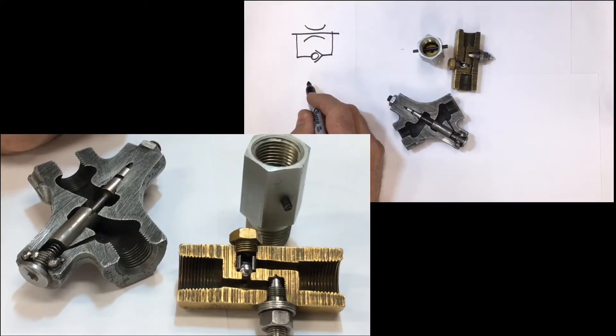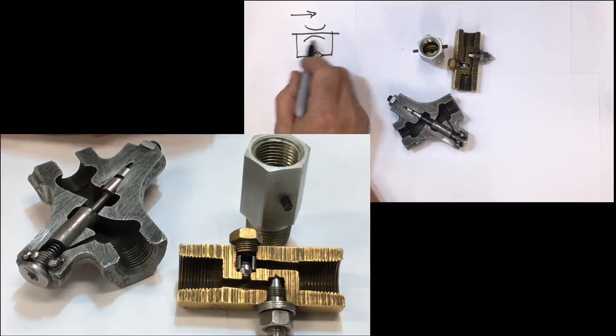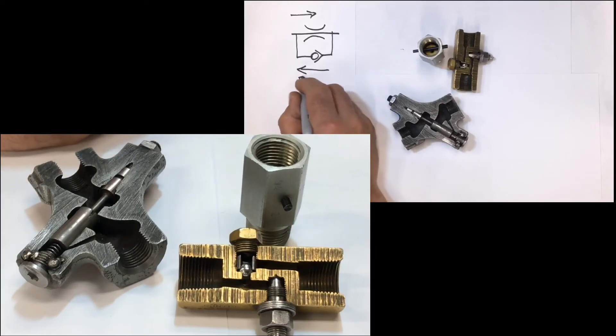So that in one direction, in this direction, it's metered. Notice that it can't pop the check ball off its seat, so it has to go through the orifice, but in this direction right here, it's free flowing.